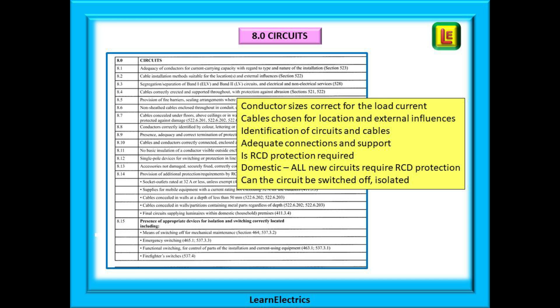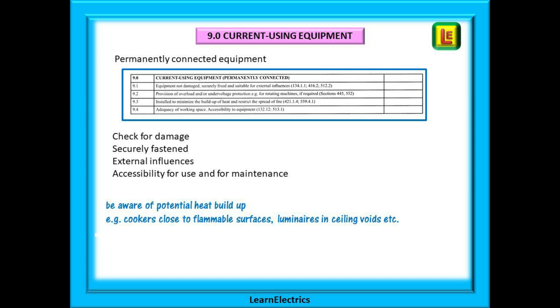Section 8 is a biggie — it spans across page one and page two and is all about the circuit you have just installed. Take each item one at a time. For example, 8.1 asks whether the conductors are the right size for that circuit — generally we will have used the tables in the On-Site Guide to select these. Item 8.8 asks if the cables are correctly identified: is the phase wire brown, is the neutral blue? Item 8.14 asks whether RCD protection is needed for the circuit, and 8.15 asks whether we can turn the circuit off for maintenance.